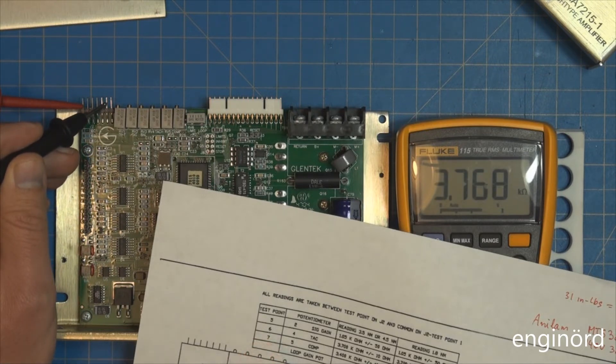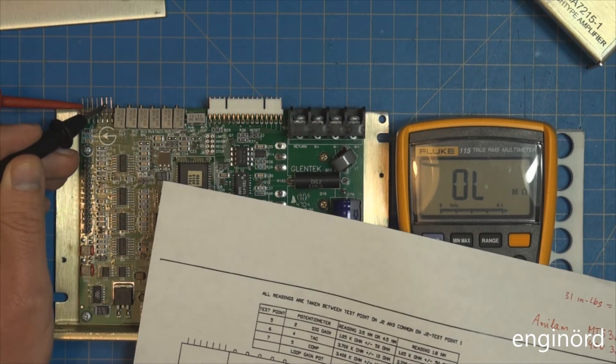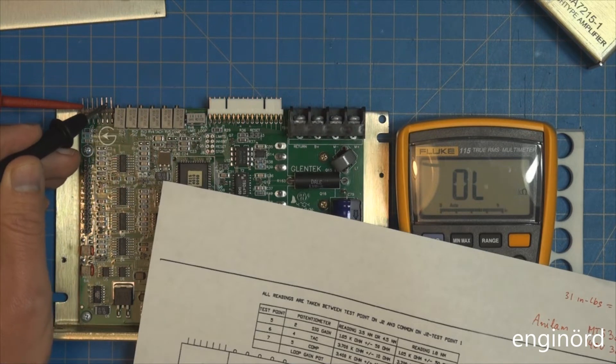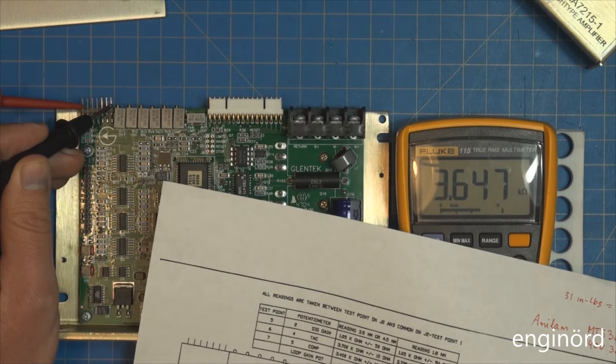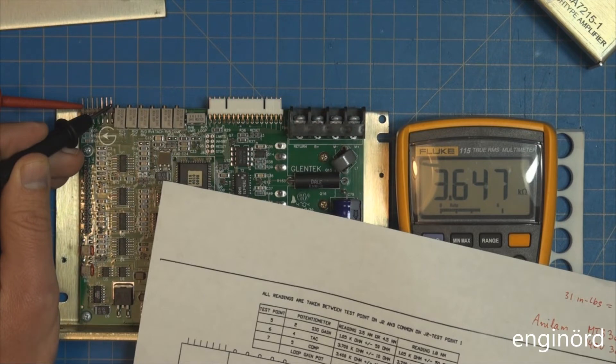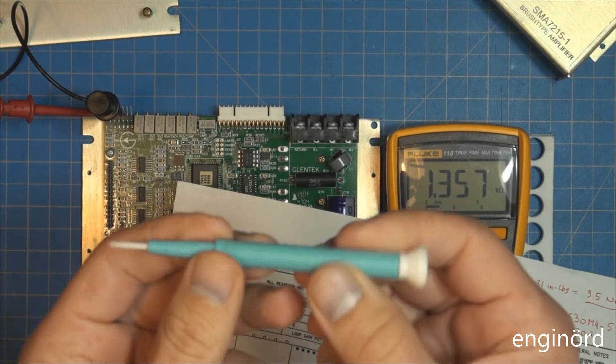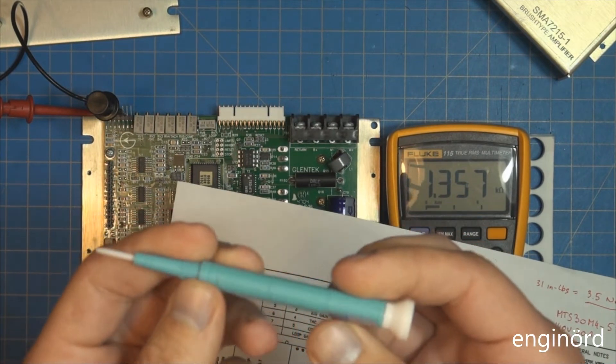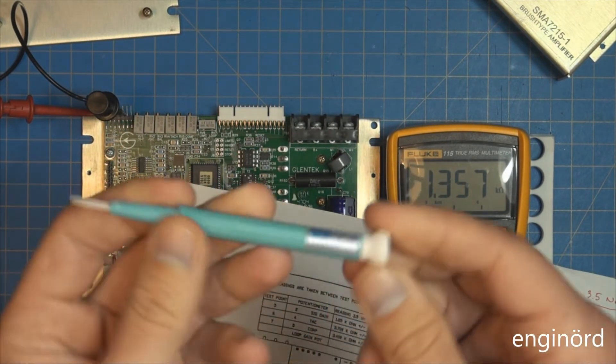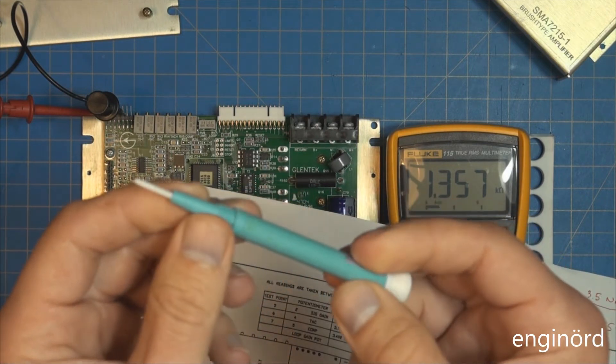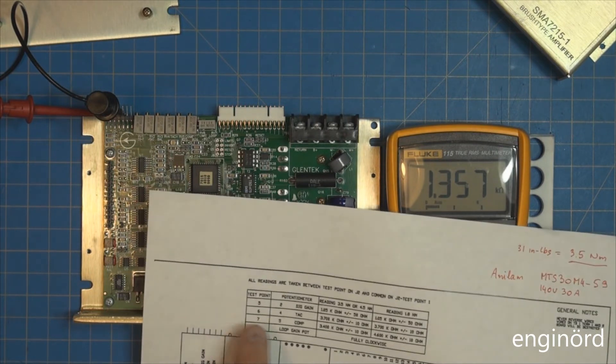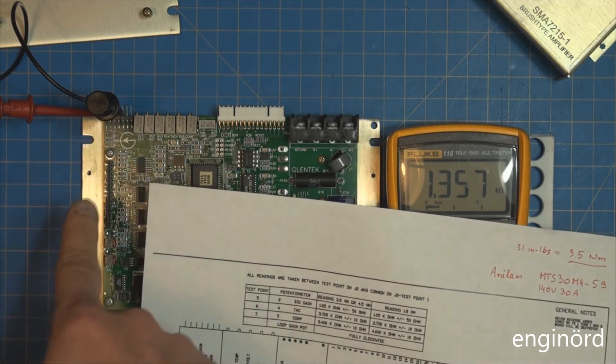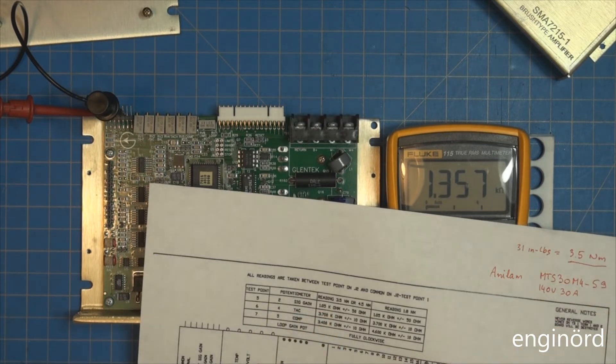The next test point is 6, and that is requiring 3700 ohm. You can see it's pretty much there - 3768. Then number 7 right here is supposed to be 3400, and it's 3600. I'm going to do the adjustment. I got one of these ceramic screwdrivers - one of the best investments I ever did, great for jobs like this.